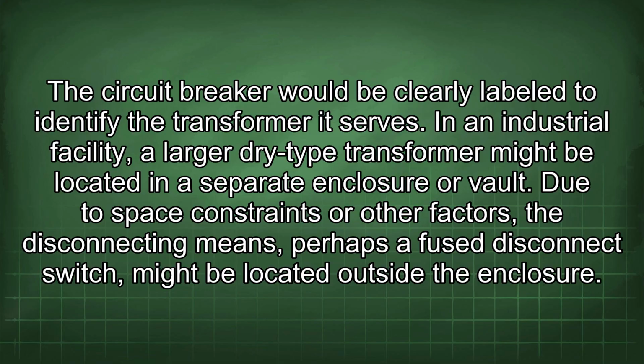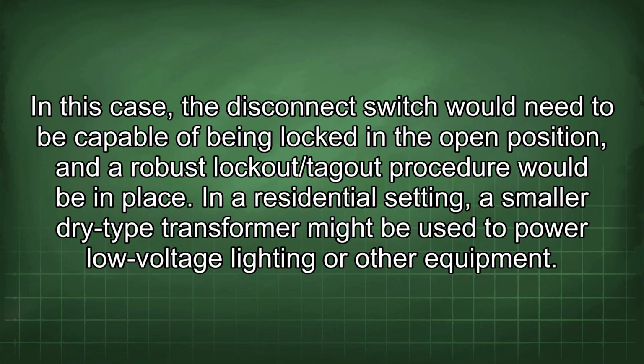In an industrial facility, a larger dry-type transformer might be located in a separate enclosure or vault. Due to space constraints or other factors, the disconnecting means, perhaps a fused disconnect switch, might be located outside the enclosure. In this case, the disconnect switch would need to be capable of being locked in the open position, and a robust lockout/tagout procedure would be in place.